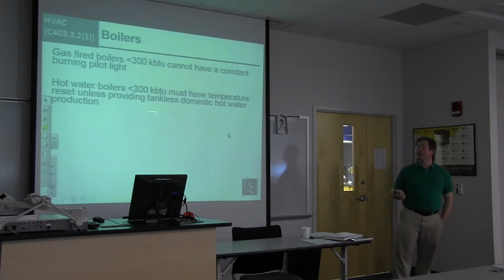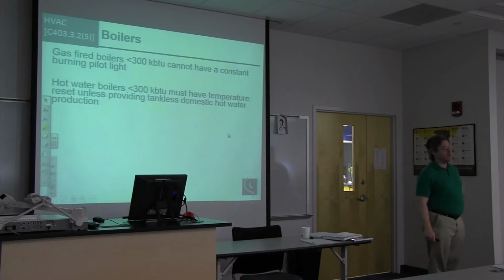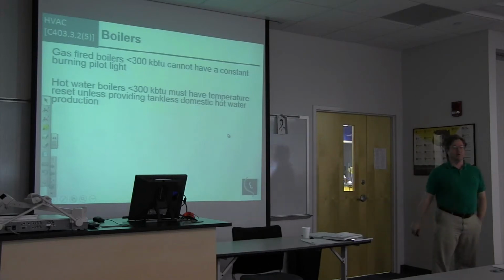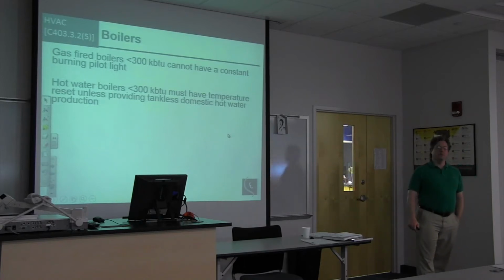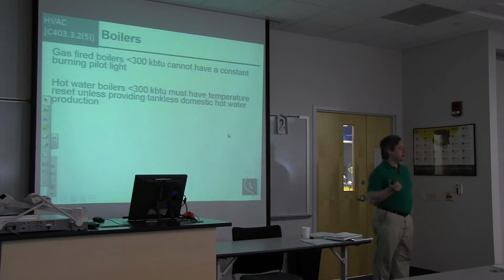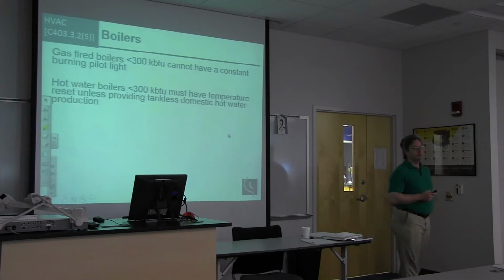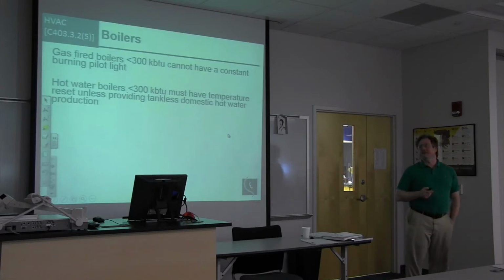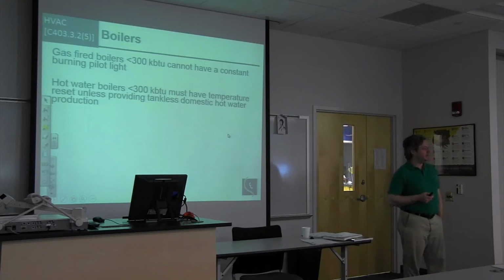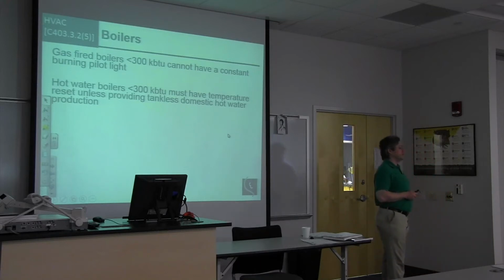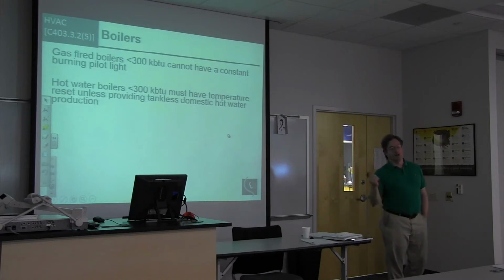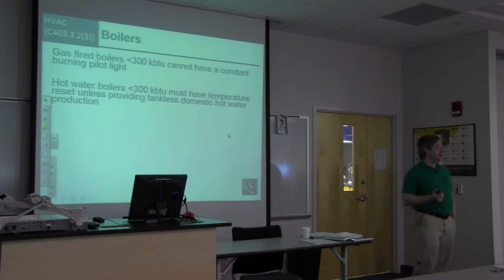So temperature setback for outdoor air or some other load methodology. Now, there is an exclusion if they're providing tankless domestic hot water off that boiler, then you don't have to do your temperature reset on that. But again, controls tend to continue to get better and cheaper. And so, looking at what's cost effective, putting this on, a lot of boilers just come with this by default.